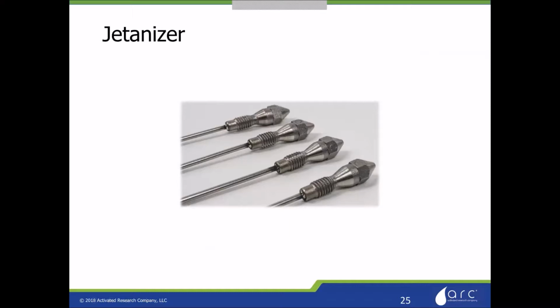So with that, I want to shift gears a little bit to our Jetanizer product, because I want to leave some time at the end for questions. So the Jetanizer was our attempt to take on the methanizer head-on. When the Polyarc first came out, we got a lot of feedback that said, hey, this is just a methanizer, this is just going to replace my nickel catalyst methanizer. And they were kind of missing the point that the Polyarc will convert CO and CO2 to methane like a nickel catalyst methanizer, but it will also convert everything else to methane and give you that uniform response. And so we invented the Jetanizer because we realized there was a market for people that were just looking for CO and CO2, and they wanted a cheap and simple solution to do that.